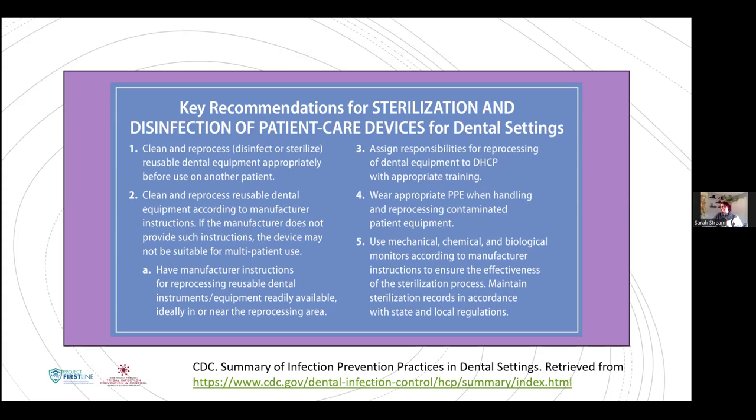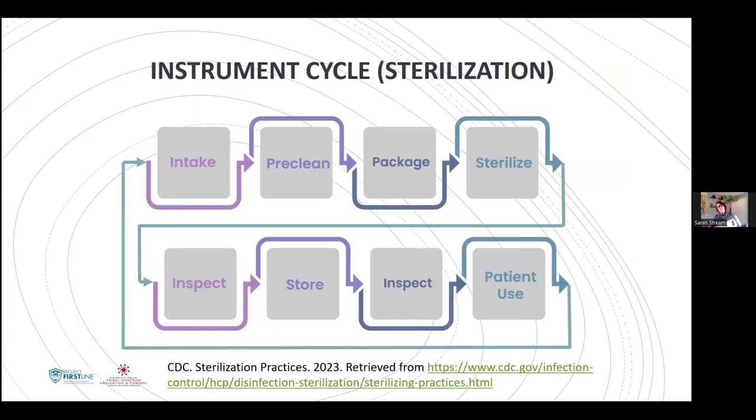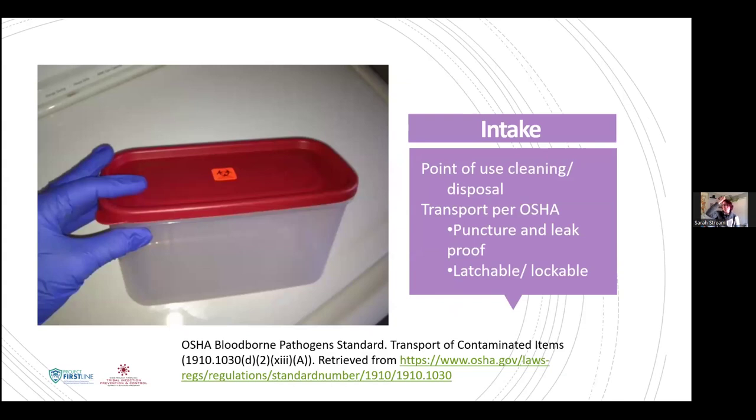So because this is such a complex process, we're going to go through it step by step, and it really is an instrument cycle. It starts with patient use and intake, and instruments are continuously going through this cycle of intake, pre-cleaning, packaging, sterilization, inspection, storage, more inspection, and then patient use. And each step is very involved, really.